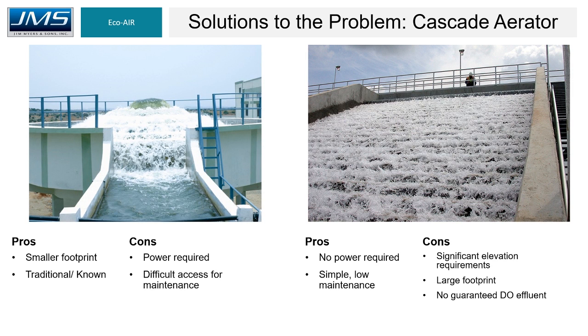On the left, the vertical tray style cascade aerator offers a smaller footprint. However, its cons include a pump being required — which means ongoing energy costs — as well as difficult access for maintenance. On the right, the traditional step-down cascade aerator requires no power and is simple with fairly low maintenance. However, its cons include the requirement for a significant elevation drop, a large footprint, and most importantly, it does not guarantee a DO effluent at the outfall.